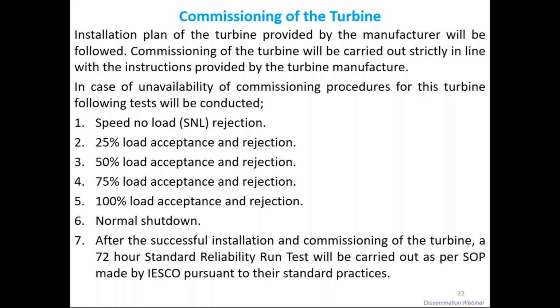Then number two, 25% load acceptance and rejection. It means apply the 25% load on the turbine and same as then reject it, and turbine should be normal. Then 50% load acceptance and rejection, then 75% load acceptance and rejection, and then 100% load acceptance and rejection. It means if 100% load is applied, everything should be running normal, and if 100% load is rejected, then everything will be running normally, and then normally shut down.